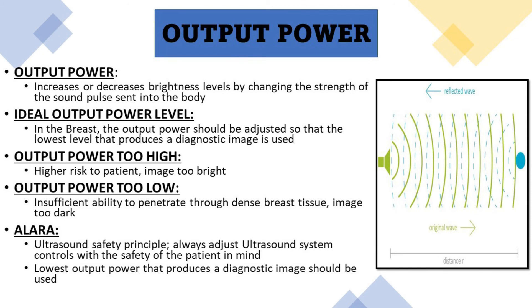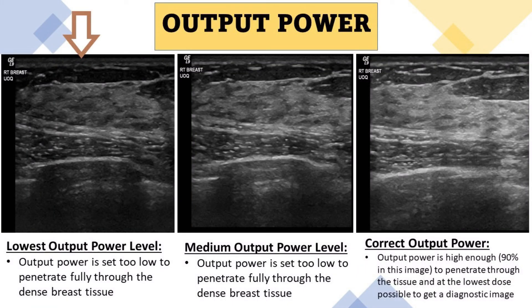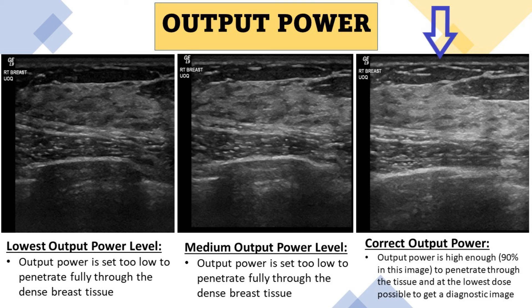It's important when operating an ultrasound machine to abide by the ultrasound safety principle of ALARA — as low as reasonably achievable. Always adjust the ultrasound system controls with the safety of the patient in mind; the lowest output power that produces a diagnostic image should always be used. In the first image, the output power is set too low and doesn't fully penetrate through the dense breast tissue. In the next image, the output power is turned up to a medium level but is still too low to penetrate fully. In the last image, the correct output power has been achieved, set at 90%, penetrating fully through the tissue.